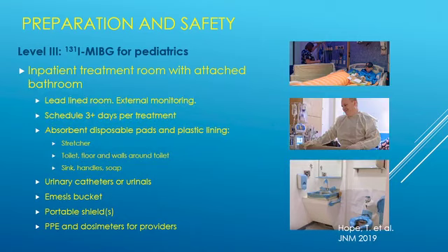All right, level 3, this is really hardcore. I-131 MIBG for pediatrics. This requires a whole lot of preparation, and to be honest, we don't do that at our facility. This definitely requires a lead-lined room. This is almost the equivalent of a typical therapy, external beam or HDR, except the patient is going to be there for 3 to 5 days. Now, of course, the lead lining isn't going to be nearly on the same level that you have for external beam or HDR. But you are probably going to want to have some amount of external monitoring, so you don't have to go into the room every single time.